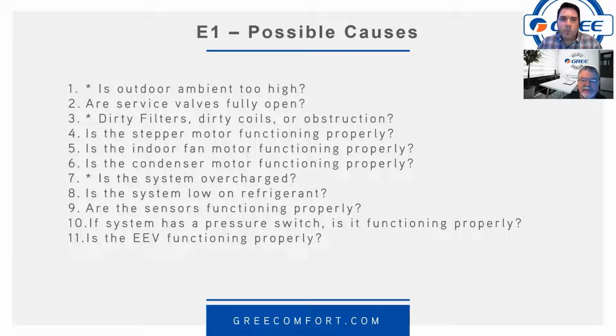And with these systems, it's just a matter of really understanding how the system operates and what things to check next. So we're going to look at the easy things first. Is the outdoor ambient temperature too high? Are the service valves open fully? Do you have dirty filters, coils, or obstructions? Is the stepper motor working properly? Indoor fan motor functioning properly? Condenser motor, and so on.